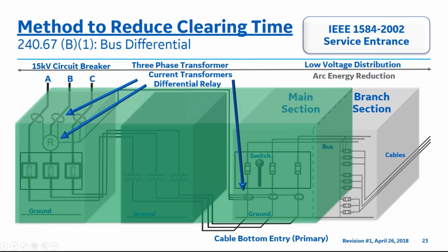The overall general practice or rule of thumb for a main switchboard section is to add roughly 5 inches of depth for line or load side transformer differential CTs that are drawn here. The CTs may have to be placed within the low voltage main fuse switch line side to leave some part of the line side unprotected by the fast 87T between the CTs and the switch.